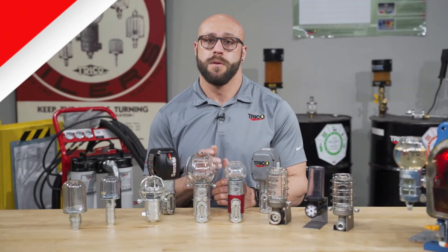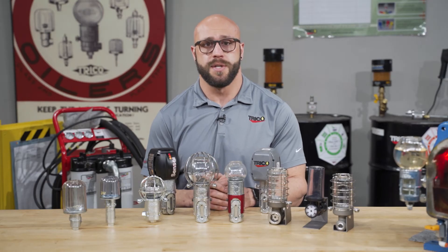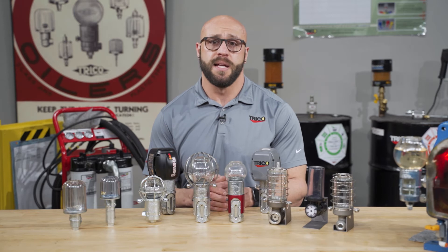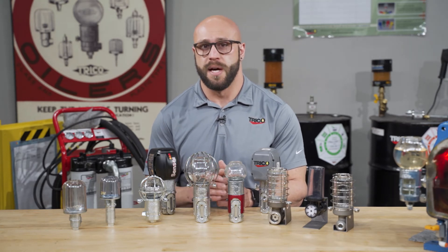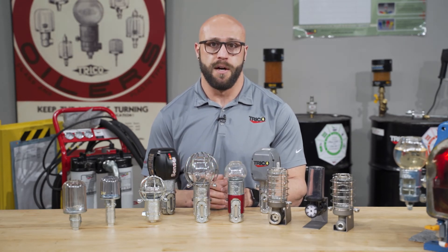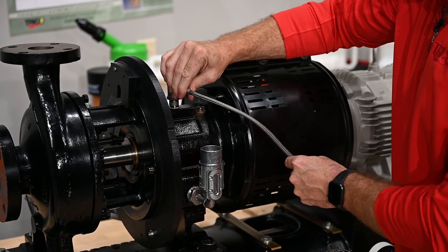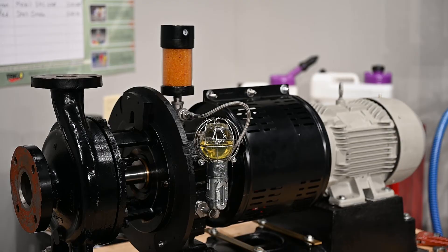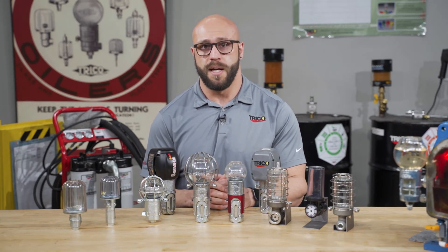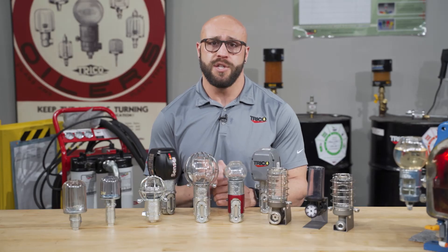Next up is the closed system oiler. The closed system oiler was introduced at the beginning of the preventative maintenance era. In most applications today, we can certainly understand that closing off your oil sump from the outside atmosphere is critical to the health of your lubricant and the life of your equipment. Back in the 1980s and 90s, this was a relatively new concept. We took the constant level principle and removed the ability for it to exchange air from the outside environment. In order for the oiler to function properly, it must exchange air somewhere. To achieve that, we pipe the surge chamber to the oil sump, thus creating a closed loop system known as the closed system oiler. This oiler is designed to be installed below the oil level of the equipment, then adjusted to the right height by way of an external collar. The oil level is equivalent to the bottom edge of this external collar, making it much easier to set the oil level.